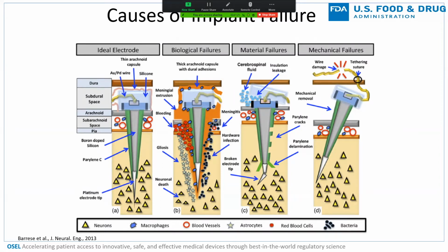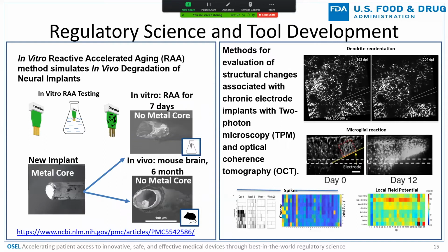And one thing I failed to mention is this is not meant to be an in-depth talk about the different activities we're doing, but just general broad strokes. So the next slide talks a little bit about some of the tools that we've developed and are developing to address some of these concerns with neurological implants. So the first one on the left is an in vitro reactive accelerated aging method. And what we've done in this case is we've looked at the implants from the perspective of, can I reduce the time frame in which I need to do an in vivo study to understand that a device is going to fail due to aging and biological response.